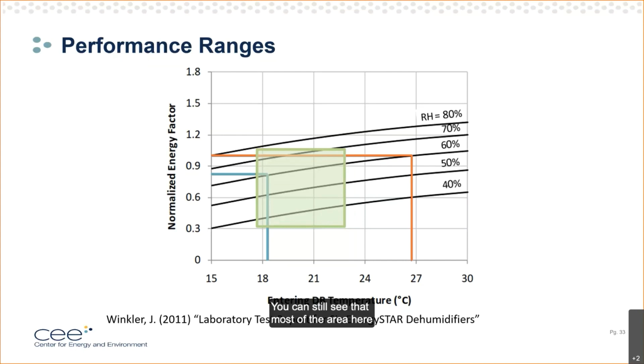On the other hand, our basement conditions in the study are represented by the green square. You can still see that most of the area here is at a normalized energy factor that's less than even the new standard. So the new standard still doesn't reflect how dry it is in our cool basements that we keep drier than 60% relative humidity.